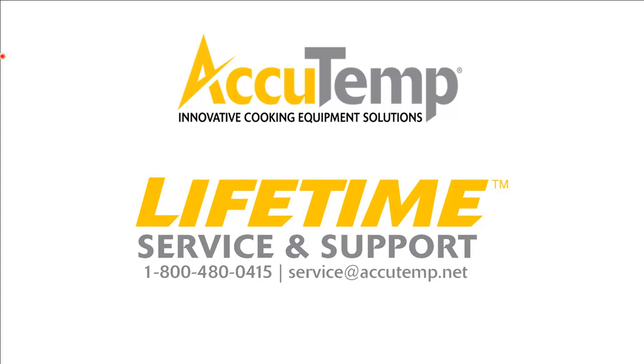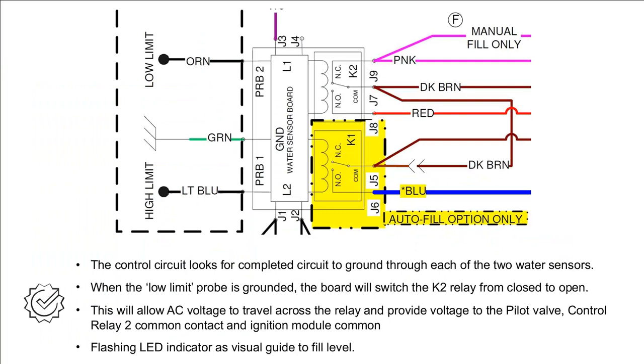If the light on the water board does not flash, now this isn't directly related to the call for heat. That light is wired to our control of the water board, which is receiving operational voltage. If that light is not flashing when you plug that unit in and you have no alarms on the front of the unit, that's overtemp, high water, low water, nothing at all, we are going to suspect the water board. Now, you would check, of course, voltage at J3 violet to ground to make sure that the voltage is being supplied to the control side of the water board. But as it's tied to the control, if voltage is there, that is a defect on the water board.